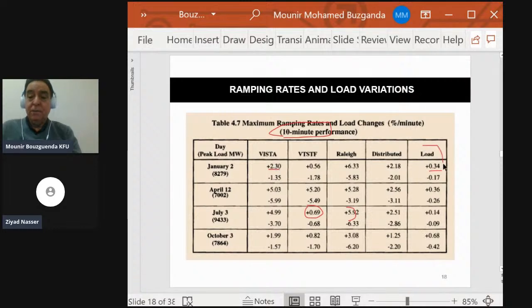So it's going to be very hard for the load or the grid to absorb all of this variation. But nevertheless, if you have a distributed system, you have smaller numbers. Here you have 2.2% versus 6. Here you have 2 versus 5, 5, 5. Here you have 2 versus 4, 5, 6 - it's much better.